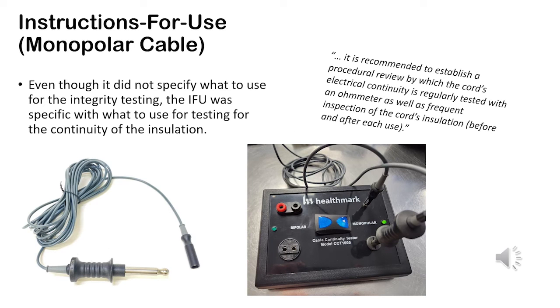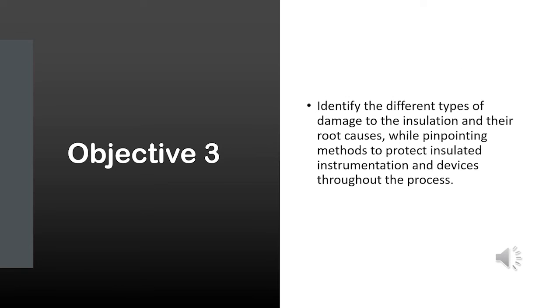The IFU for monopolar cables, the one that was reviewed, recommended establishing a procedural review by which the cord's electrical continuity is regularly tested with an ohmmeter, which the picture on the bottom shows as a cable continuity tester, as well as frequent inspection of the cord's insulation before and after each use. So let's go on to objective 3 and identify the different types of damage to insulation and their root causes.